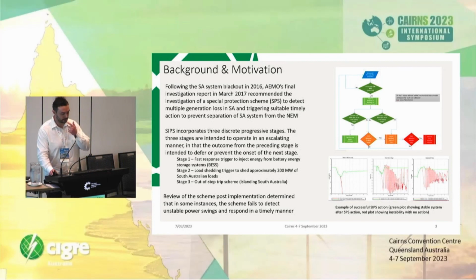The Heywood interconnector tried to pick up the slack, and the protection there, loss of synchronism protection, was activated, resulting in the islanding of the state.